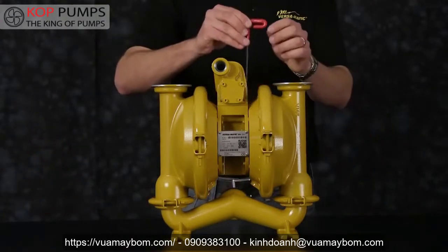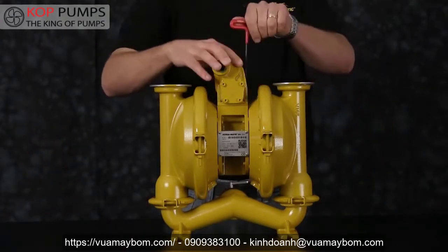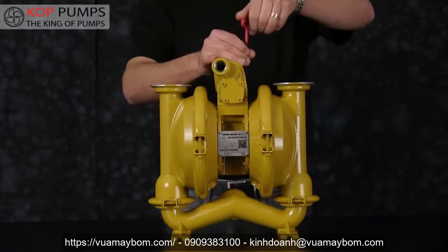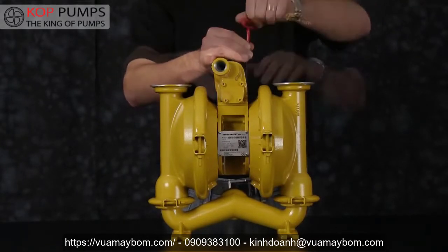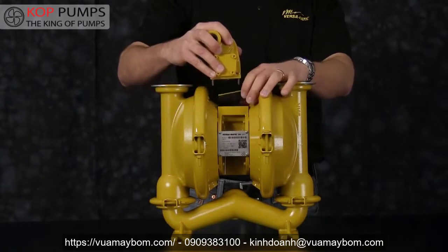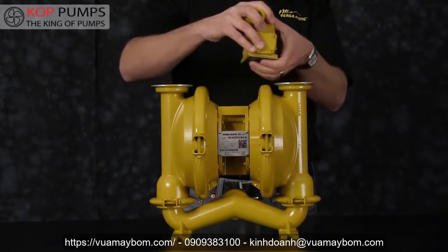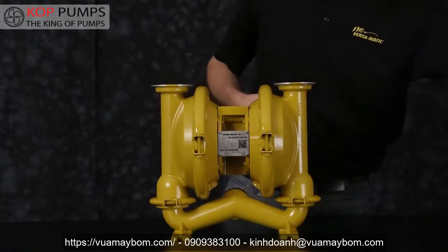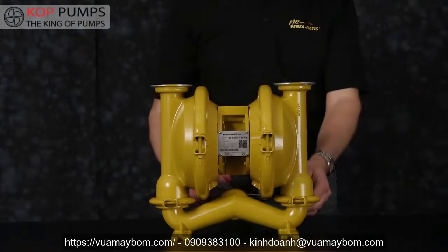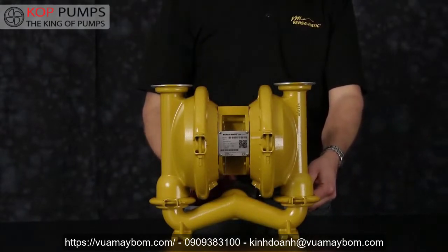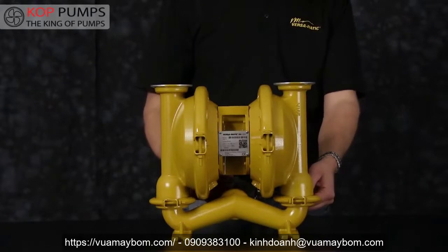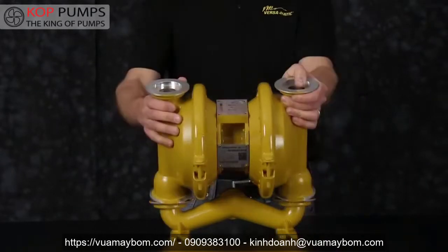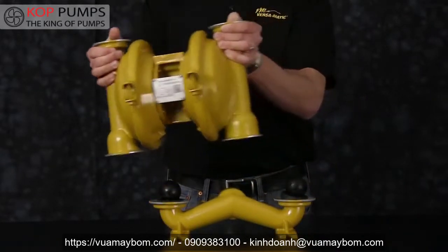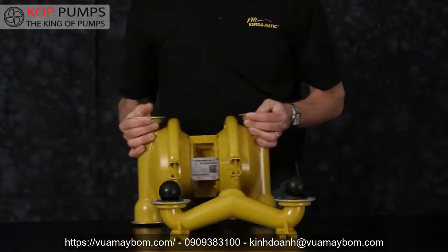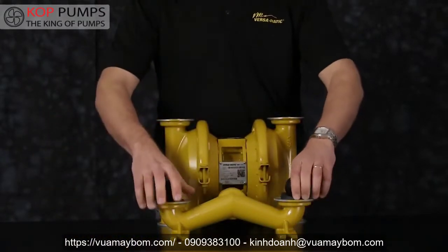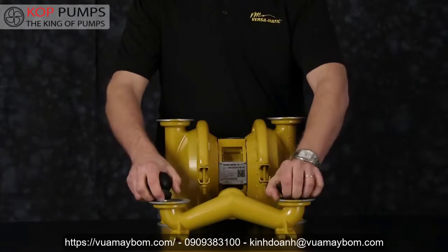Now we're going to remove our main air valve assembly. Once you remove the main air valve assembly, go ahead and set aside for later rebuild. Now remove the suction manifold. Go ahead and set the center section of the pump aside and remove the check balls and valve seats on the suction side and discard.